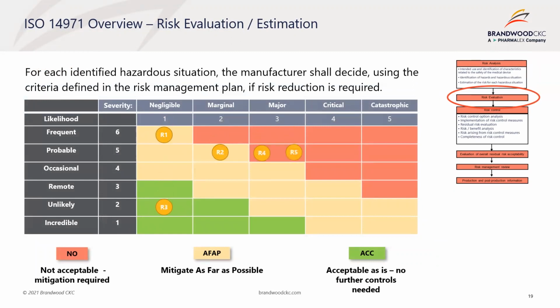Various methods can be used to estimate risk. Those methods should be examined. For example, the circumstances in which a hazard is present, the sequence of events leading to a hazardous situation, the probability of a hazardous situation occurring, the probability of a hazardous situation leading to harm, the nature of the harm that could result. Risk should be expressed in terms that facilitate decision-making on risk acceptability and the need for risk control. For example, using severity and probability scales. In order to analyze risk, these should be analyzed separately.